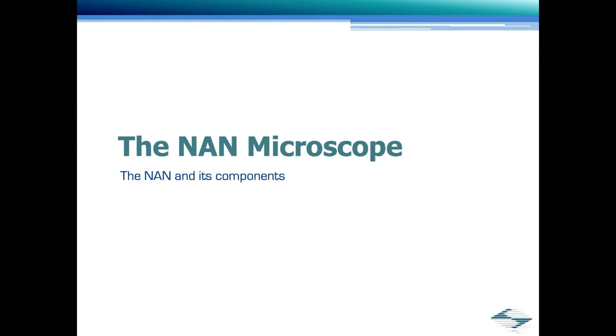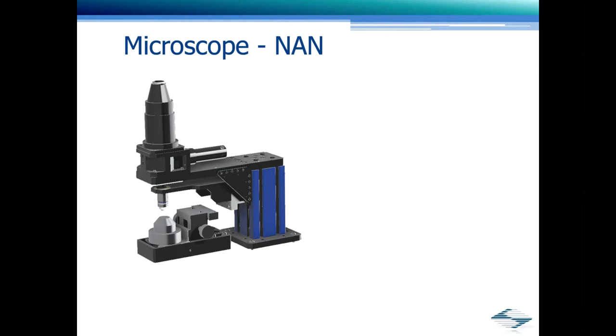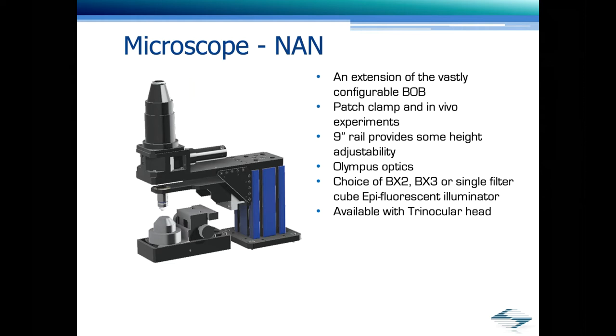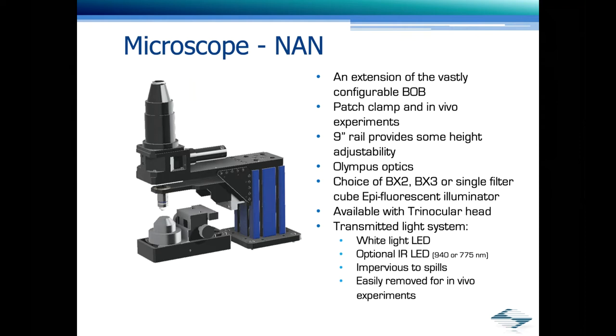Now that we have our foundation, we need to build on it by adding a microscope and its supporting components. I would like to start off with one of the newest specialized microscope, the NAN. The NAN is an extension of the vastly configurable BOB. It was designed for patch clamp and in vivo experiments. Is mounted on a 9-inch rail which provides some height adjustability. Uses Olympus Optics. You have a choice of BX2, BX3, or single filter cube epifluorescent illuminator. Available with or without a trinocular head. It includes a transmitted light system with a white light LED and with an optional IR LED available in either a 940 or 775 nanometer wavelength.